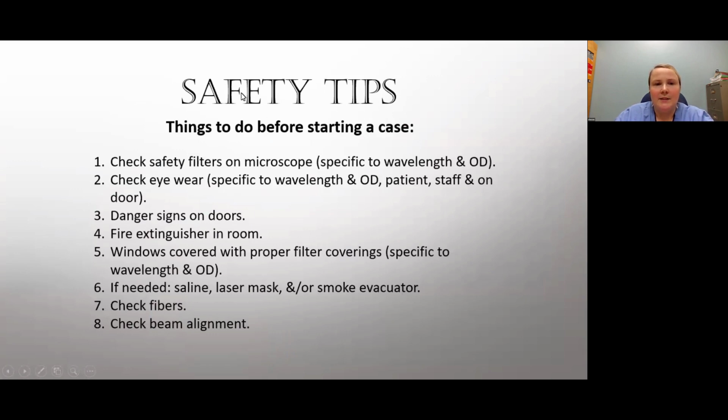So safety tips, we're going to go over things before starting a case. Check safety filters on the microscope specific to wavelength and OD. If you're using a microscope for a case, for example the Constellation where you're doing a procedure under the microscope, we do have filters, and I'll show you a picture of that soon, that go on the microscope. They're specific to wavelength and OD, so it protects anybody looking into the microscope. Instead of having to wear glasses, they can look into the microscope and will be protected.